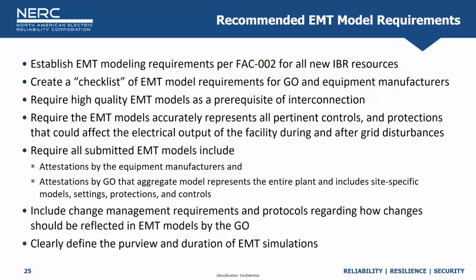Just to quickly go over some of the very highlights of the guideline. First of all, establish EMT modeling requirements for all new IBR resources. Basically, that means require, collect, vet and test EMT models for all new IBR plants. Have a checklist of EMT model requirements for GOs and equipment manufacturers so that all parties are on the same page. Require high quality EMT models as a prerequisite for interconnection. Require that those models accurately represent all pertinent controls and protections that can potentially affect the electrical output of the facility during and after disturbances. Require all models to include attestation by the OEM, and attestation by the GO that the aggregate model represents the entire plant and includes various site-specific models, settings, protections, and controls. Include change management requirements and protocols to deal with changes that should be reflected in the EMT models by the GO, and clearly define the purview and duration of the EMT simulations. Next, please.